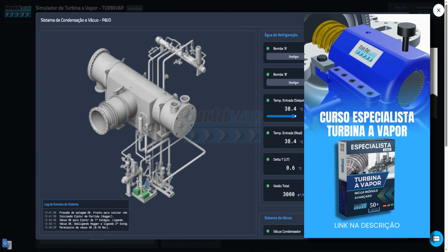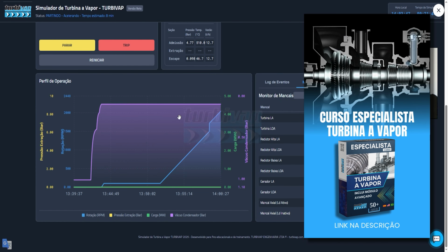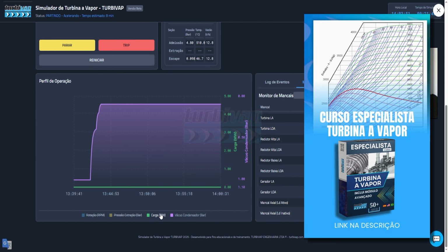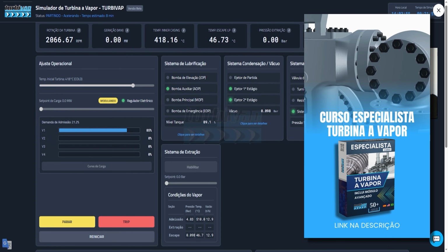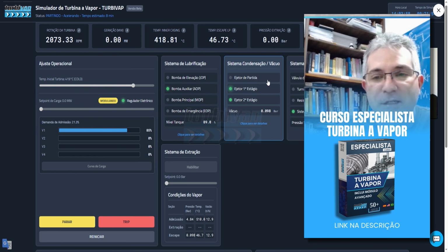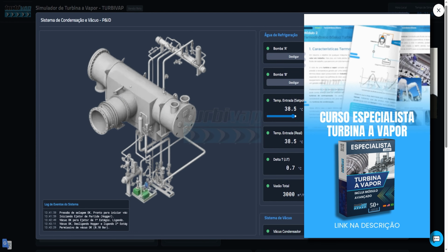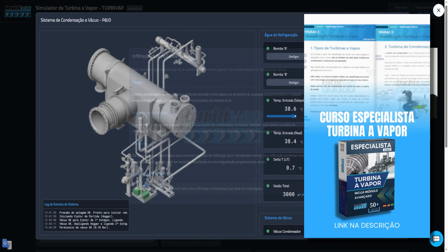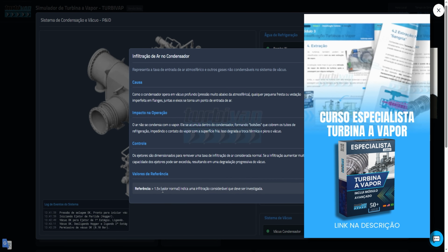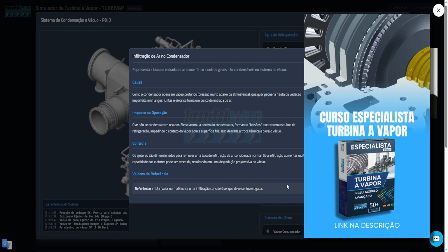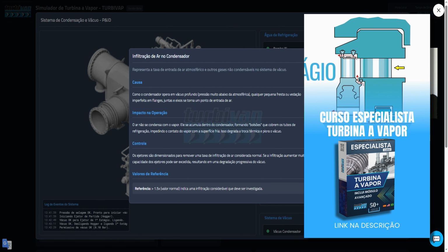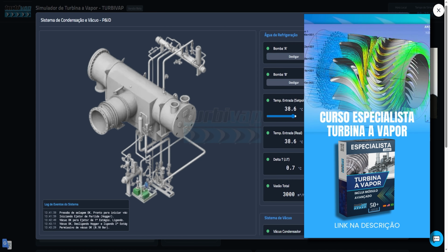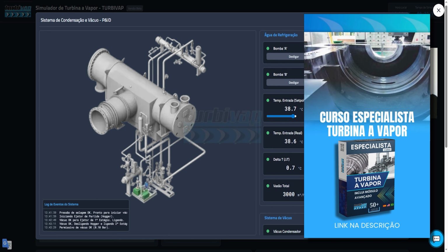It is showing that the oil is also passing, modulating the temperature valve in our vacuum system. So if you notice here, we're starting to analyze only the vacuum in the condenser. The vacuum is now in this situation. Here it is 0.09, but then we start to have a warning here. The normal reference is 1.5 times, this is indicated. A considerable infiltration, and above that it will have to be investigated, then he will start to interfere.